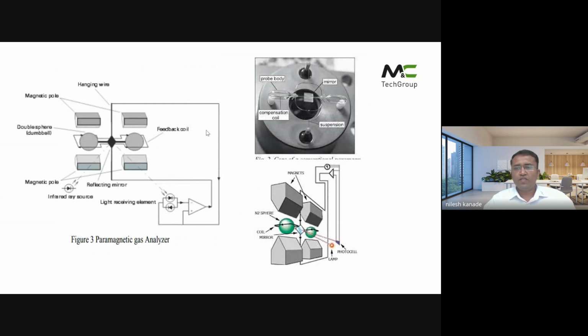In that sensor, two glass spheres are mounted between the magnetic poles, and the gases pass through these poles. The spheres deflect from their position based upon the gas's magnetic property. The gas provides a magnetic force onto the spheres and tries to deflect the glass balls. The current required to retain the position of the glass balls is proportional to the gas concentration.